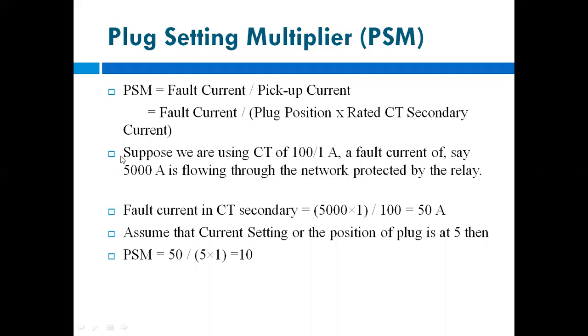So here we can write the equation as: it is equal to fault current divided by pickup current. Now we know the pickup current is equal to plug position into rated CT secondary current, right? Is it right? Yes or no? Yes. Okay, it is simple: plug position into rated CT secondary current.